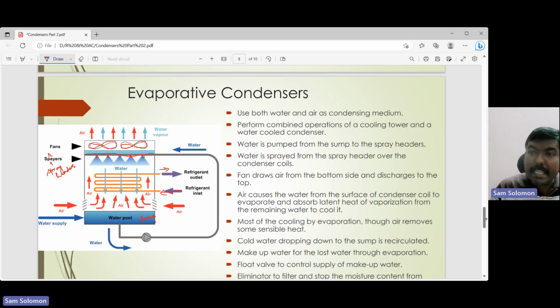Okay, the water removes heat. In addition, the air also carries away the heat. And in addition to that, you will have something called an eliminator over here. The eliminator is something like a filter. It makes sure that the water droplets do not pass along with the air. It filters the moisture content and makes sure that the water is brought back to the water sump or water pool.